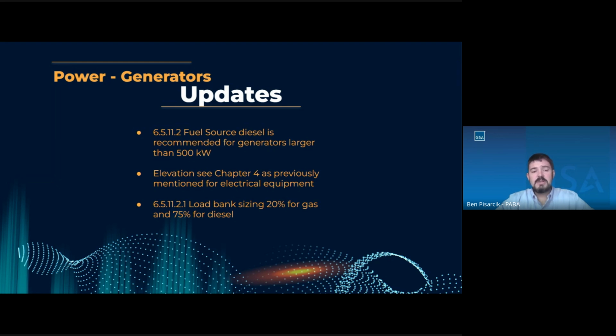The elevation of the generator and other critical electrical gear, I think I might have skipped over that previously, is now consolidated in Chapter 4. So if you were used to going to Chapter 6 to see the floodplain requirements for a generator, switchgear, and those sorts of things, that's now all been consolidated under Chapter 4. Load bank sizing: we have 20% for gas and 75% for diesel. We just wanted to be consistent with NFPA 110, and we also wanted to provide some load for a gas unit.